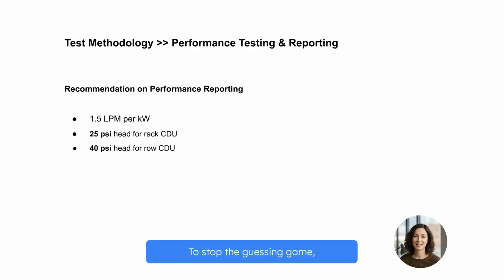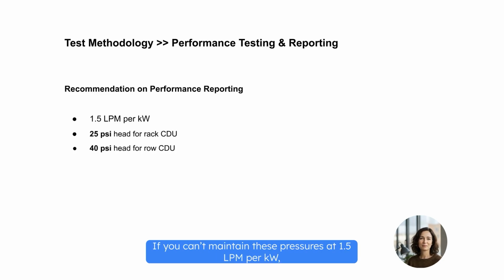To stop the guessing game, we recommend a standardized capacity rating. The industry golden rule for flow rate is 1.5 LPM per kilowatt. At this flow, your CDU must deliver specific pressure heads to be compliant. For in-rack units, we mandate a minimum 25 psi head. For larger in-row units, that requirement jumps to 40 psi. If you can't maintain these pressures at 1.5 LPM per kilowatt, your capacity claim is invalid.